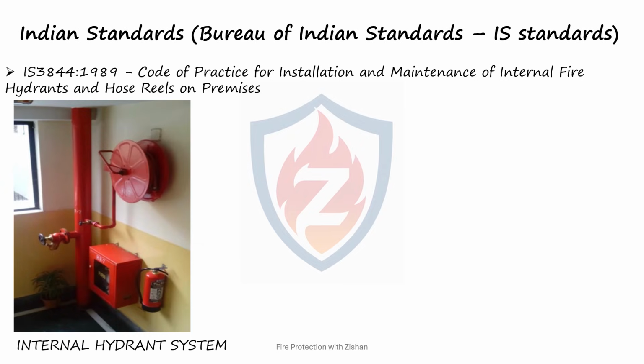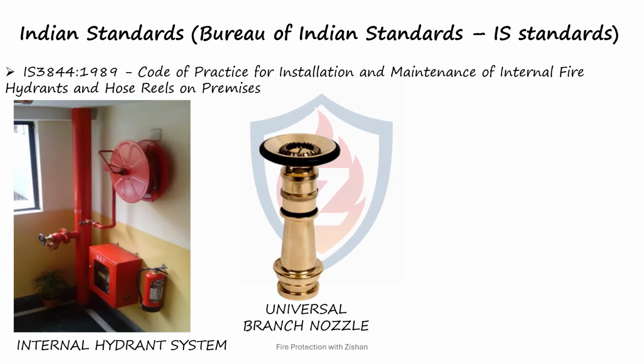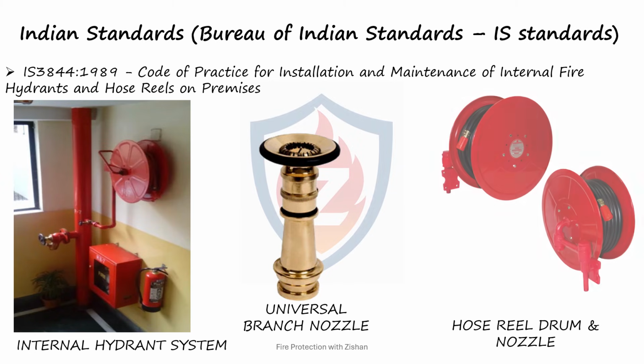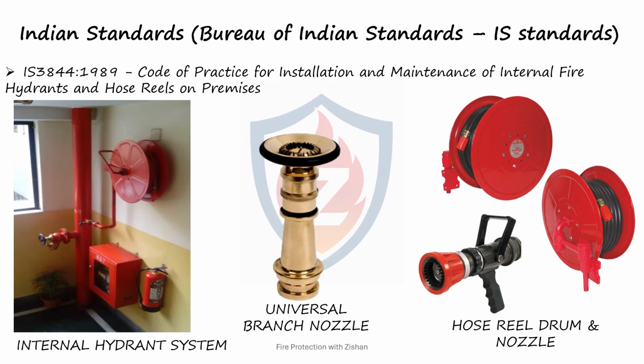In the center is the universal branch nozzle, an important firefighting component connected to the hose line. The nozzle allows firefighters to control the direction and pattern of the water stream, enabling effective firefighting operations depending on the nature and size of the fire. On the right, we can see the hose reel drum and nozzle. The hose reel provides a continuous water supply through a permanently connected hose, making it quick and easy to operate. It is particularly useful for controlling incipient, or small-stage fires, before they grow into major incidents.